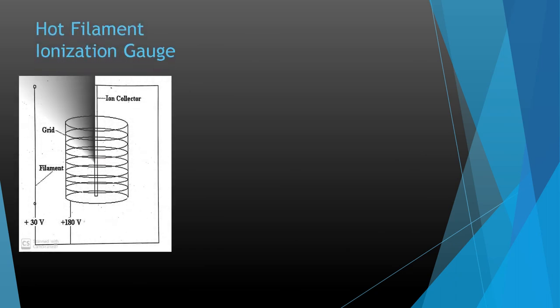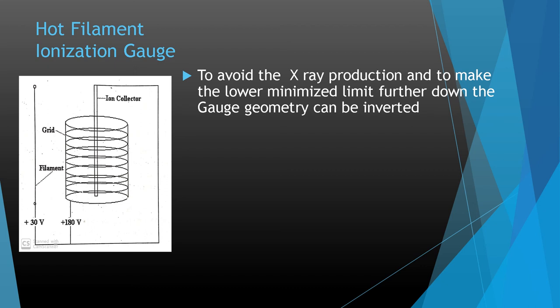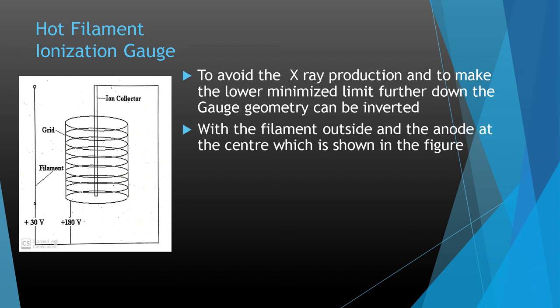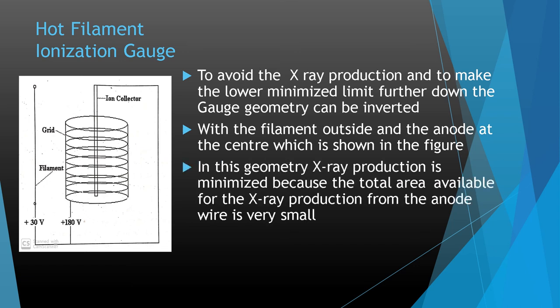To avoid X-ray production and to extend the lower pressure limit further, the gauge geometry can be inverted — the filament is placed outside and the anode at the center, which is the inverted arrangement used for the hot filament ionization gauge. In this geometry, the total area available for X-ray production from the anode wire is very small, and thus X-ray production is minimized.